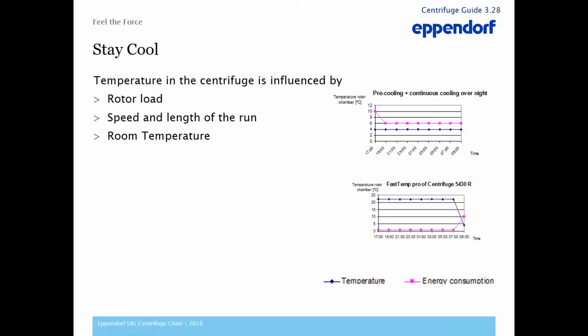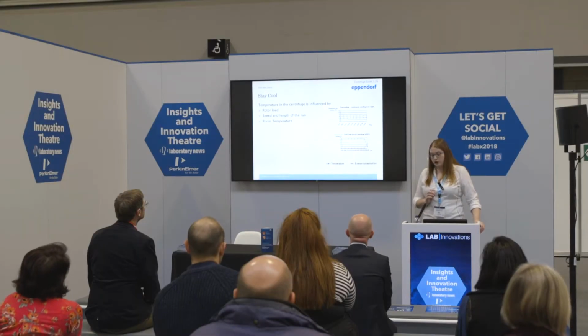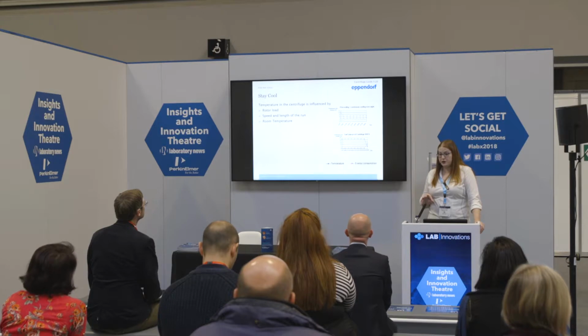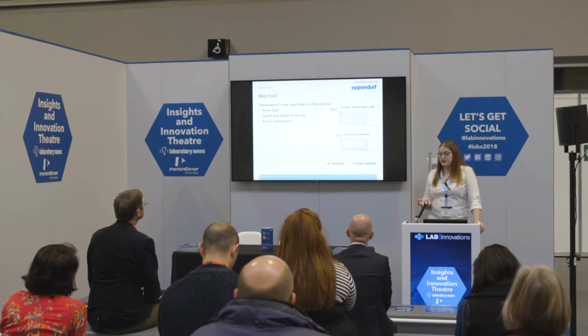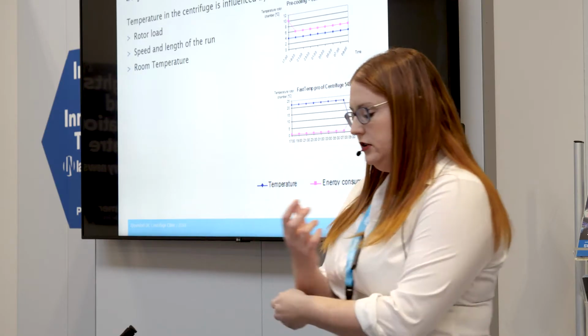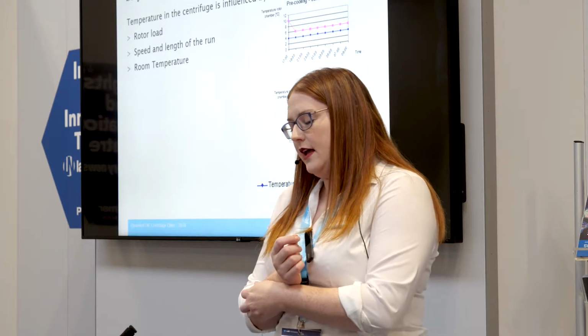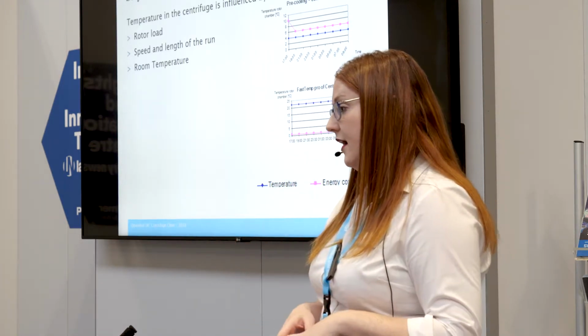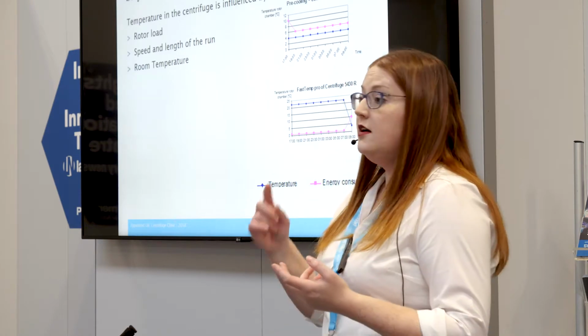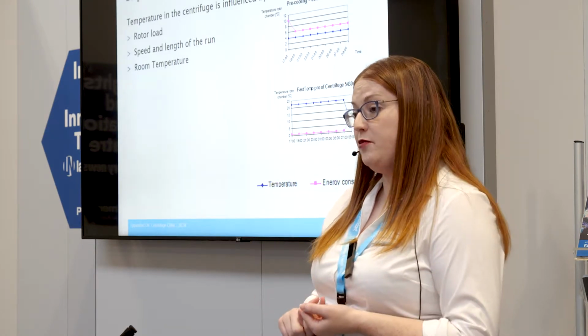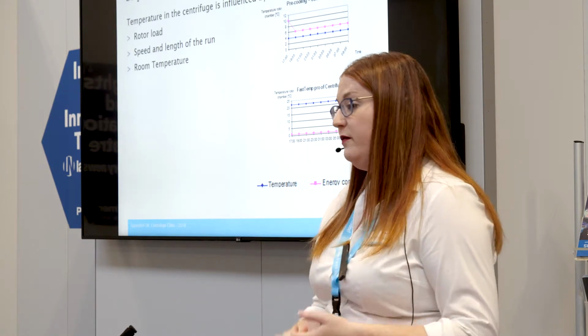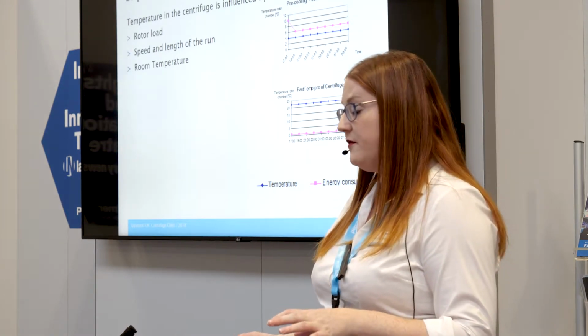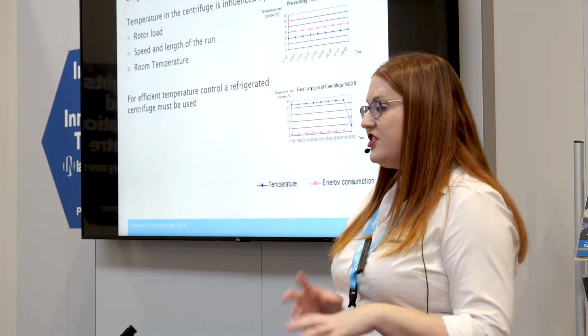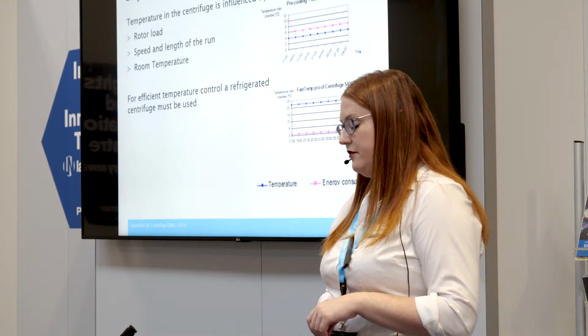So, the other things to think about with your centrifuge and looking after them, the maintenance, and making sure that you're using the most appropriate equipment for your experiments is the temperature control. So most non-refrigerated centrifuges have some sort of air cooling to stop them from overheating, but there's no active control. And the temperature in the centrifuge can be influenced by rotor load, the speed and the length of the run, and the room temperature. So the longer it's running in a warm room, the hotter it's going to get, and air cooling can only do so much. So, if you actually need temperature control, you need to use a refrigerated centrifuge.